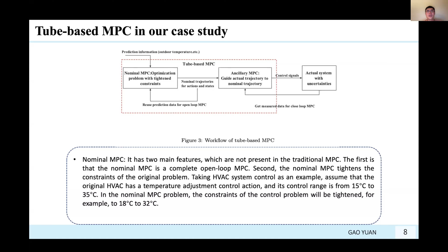This is also the idea from the original paper of tube-based MPC. For example, in BOPTest control, we may have the control range for the inlet air temperature from 15 to 35. But in the nominal MPC, we need to narrow our action space, for example from 15-35 to 18-32. This will ensure the convergence of the ancillary MPC and the tube-based MPC, the whole framework.